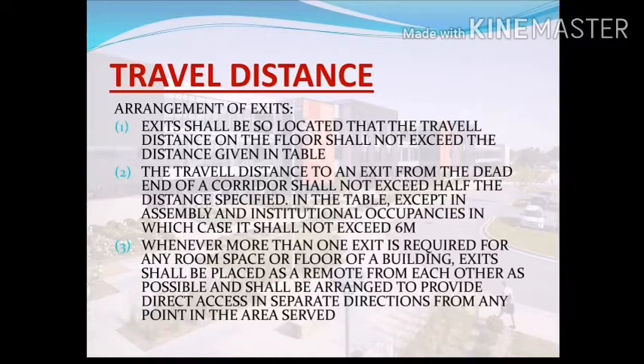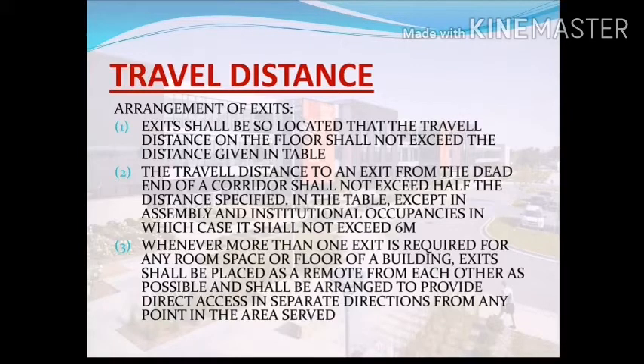The travel distance is referenced in Table 2 as per the National Building Code. The travel distance from the dead end of a corridor to the exit shall not exceed half the distance specified, except for assembly and institutional occupancies, in which cases it shall not exceed six meters. Whenever more than one exit is required for any room, space, or floor of a building, exits shall be placed as remote from each other as possible and arranged to provide direct access in separate directions from any point in the area served.